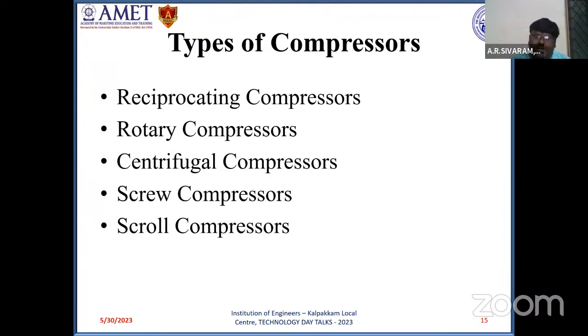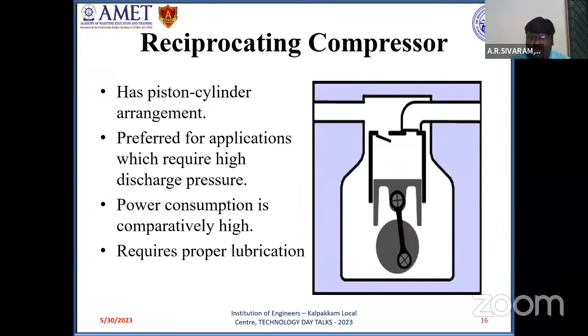Next, we will see a detailed outline of different types of vapor compression refrigeration (VCR) system components. Compressors: based upon design and working principle, refrigeration compressors can be classified into 5 types: reciprocating, rotary, centrifugal, screw, and scroll. Out of these, reciprocating type compressors are preferred for applications which require high discharge pressure, and the working of a reciprocating compressor has 2 strokes.